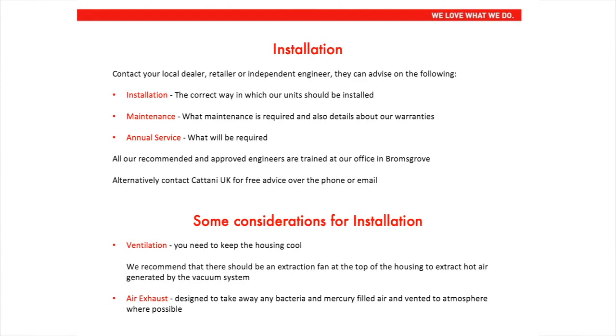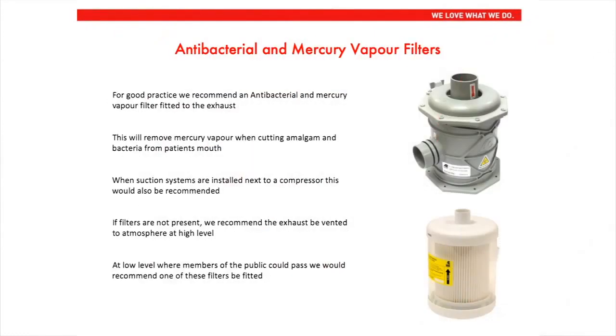Some considerations for installation. Ventilation. You need to keep the housing cool. We recommend that there should be an extraction fan at the top of the housing to extract hot air generated by the vacuum system. Air exhaust. Designed to take away any bacteria and mercury filled air and vented to atmosphere where possible.